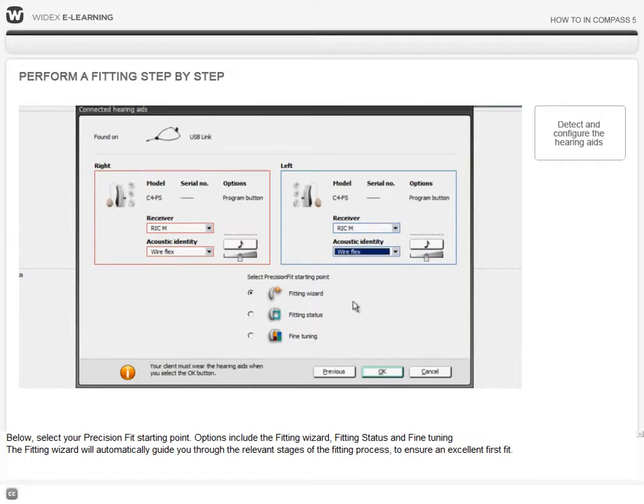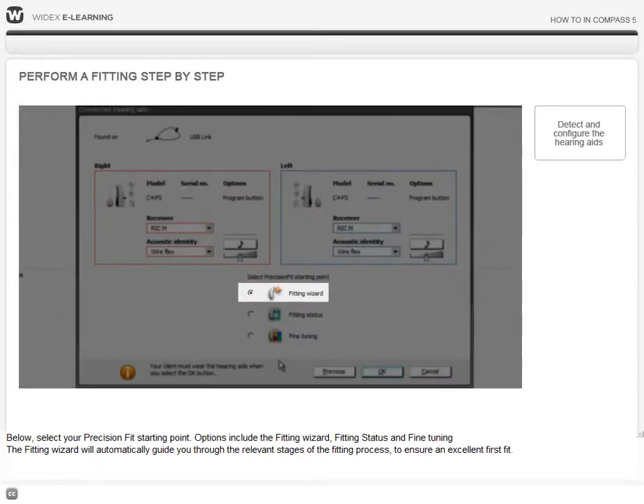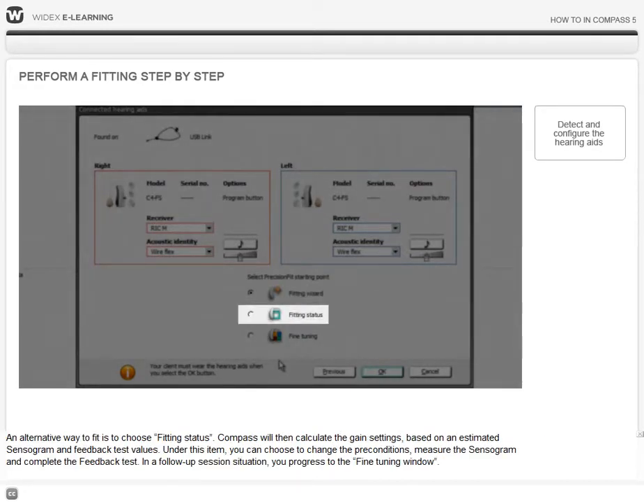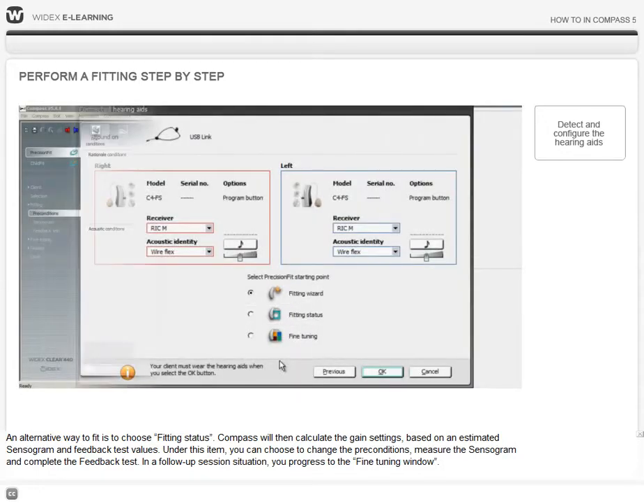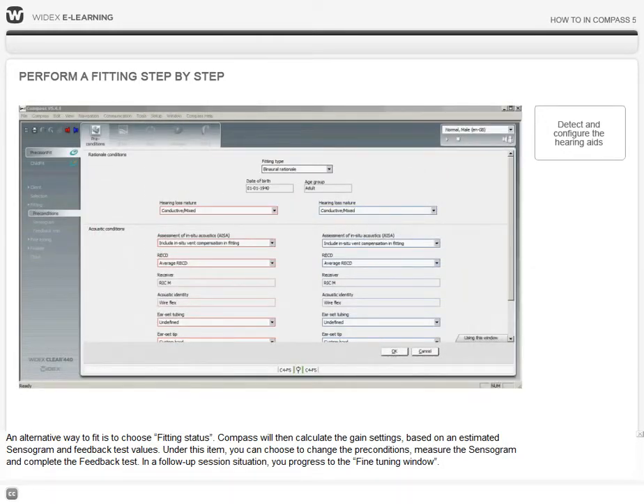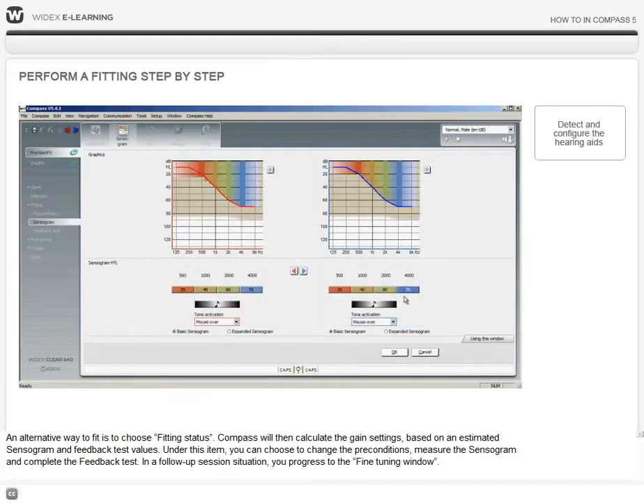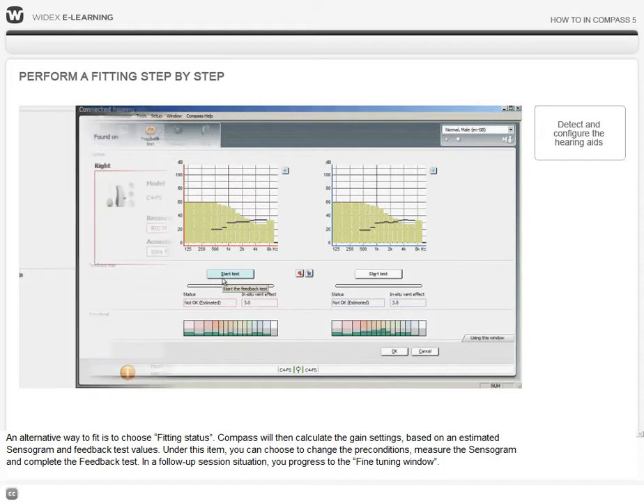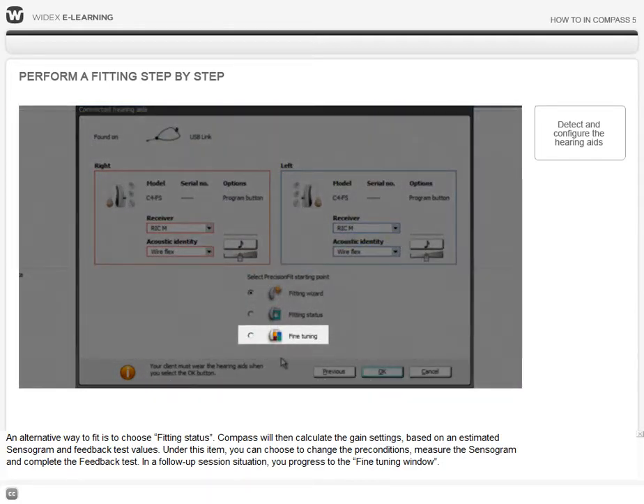Below, select your precision fit starting point. Options include the fitting wizard, fitting status, and fine-tuning. The fitting wizard will automatically guide you through the relevant stages of the fitting process to ensure an excellent first fit. An alternative way to fit is to choose fitting status. Compass will then calculate the gain settings based on an estimated Sensogram and feedback test values. Under this item, you can choose to change the preconditions, measure the Sensogram, and complete the feedback test. In a follow-up session situation, you progress to the fine-tuning window.